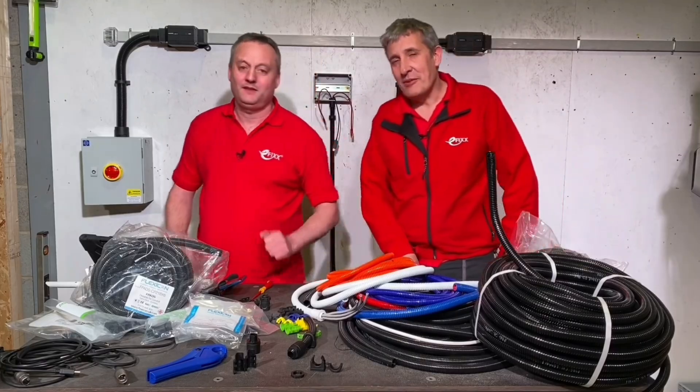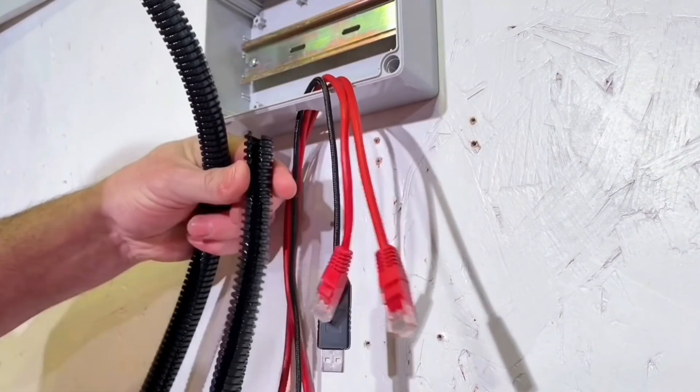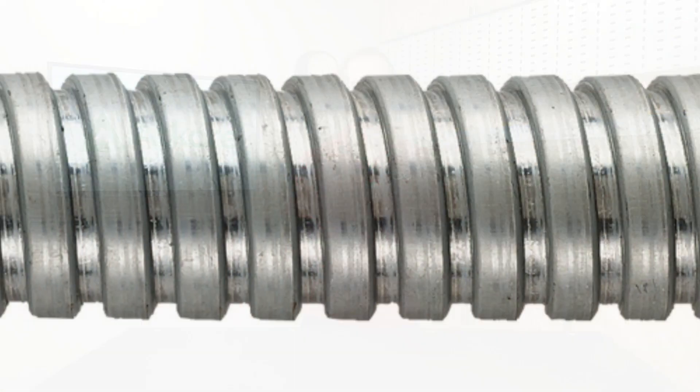This question relates to the video that Gary and Gordon produced on Atkore's excellent split flexible conduit — it really is an excellent product and video, so check it out if you haven't already. The conduit in that video is made out of plastic, and so that enables us to answer this question with a very firm no: it will not be suitable for use as a CPC.